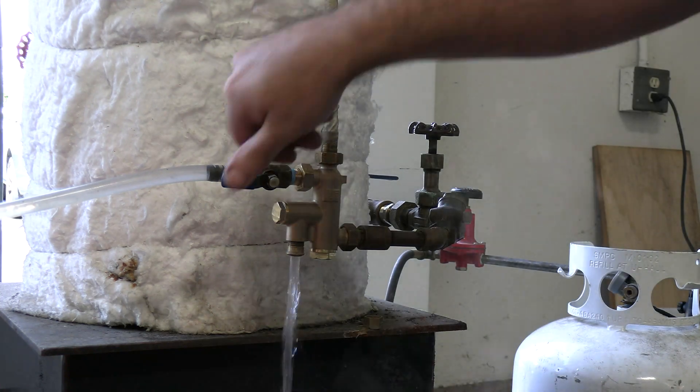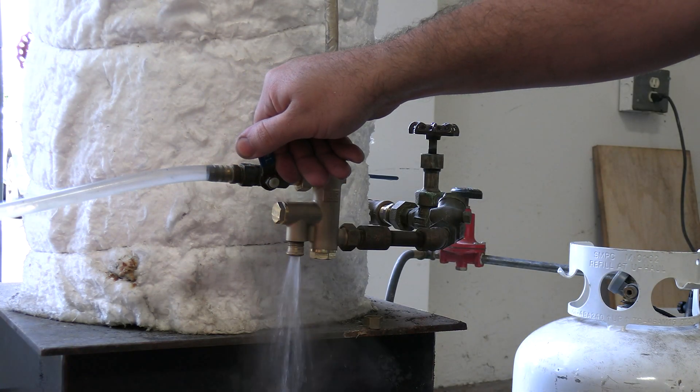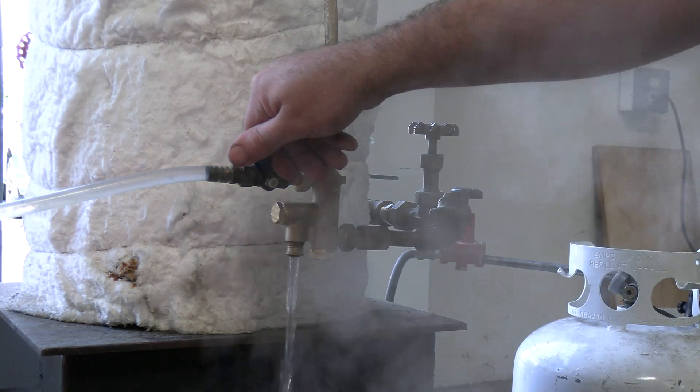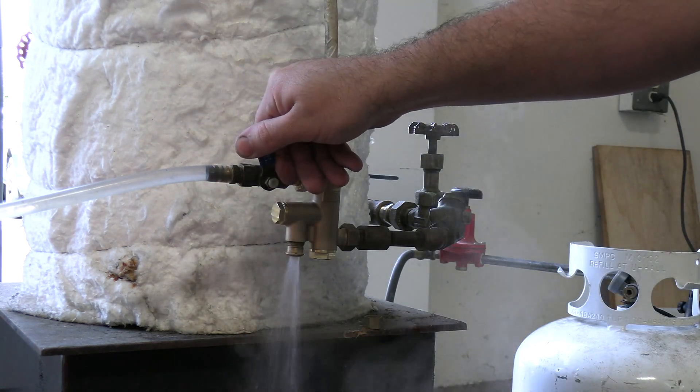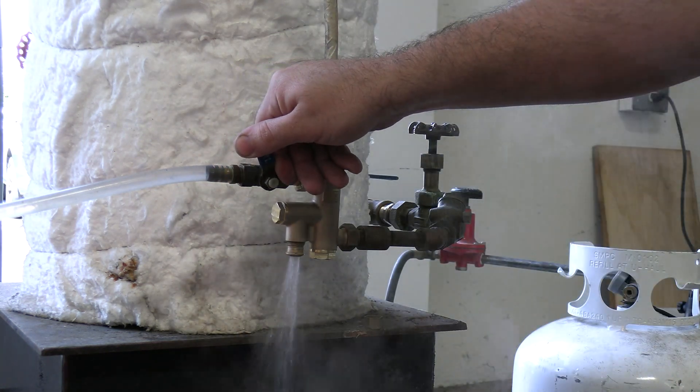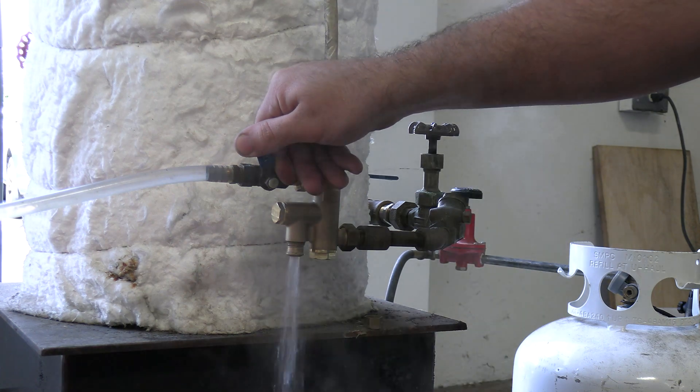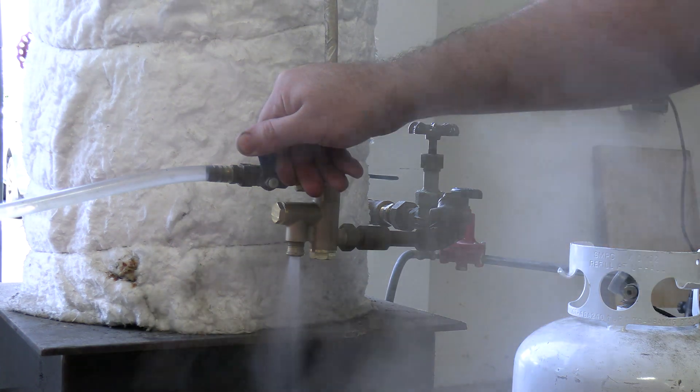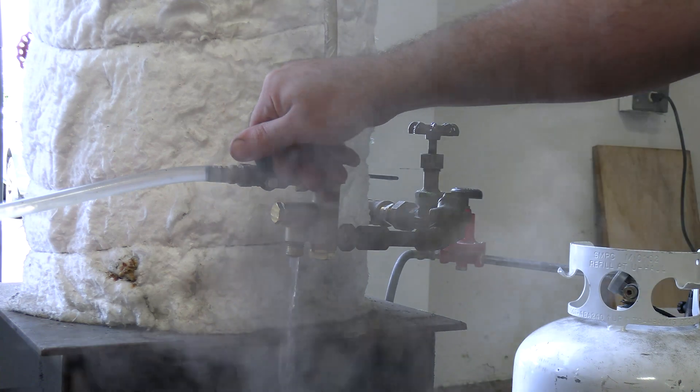The overflow behaves similarly to the closed check valve, but notice there's no vibrating hammering stage, or even a smoothing out stage. The overflow just goes from a relatively gentle flow directly to a steam and water mix. Also, there's no gurgling like we observed with the air leak.